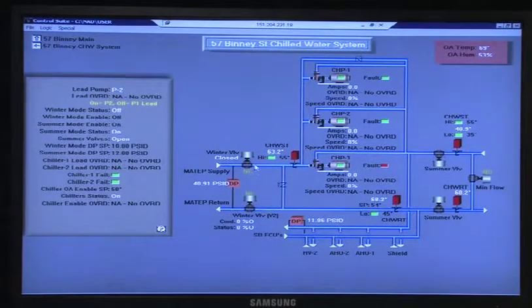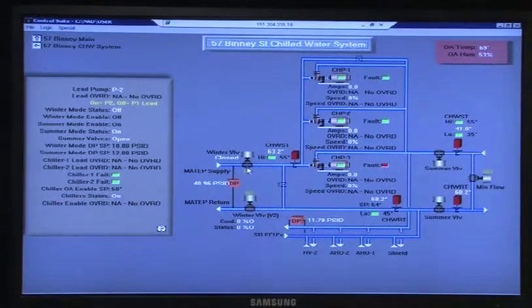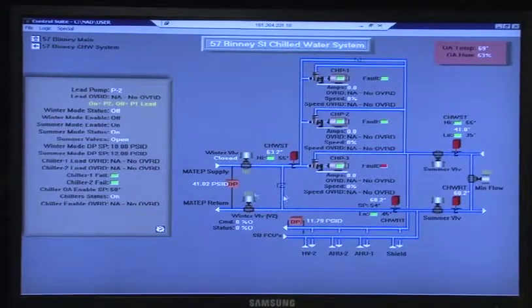So I'm going to talk a little bit about the summer, winter valve business in a minute, how this thing actually is automated and switched over. This is how it all happens. When you switch over from our chillers to MATEP chillers, it's this screen right here. This valve here is normally, not normally anyways, it's not closed, but in the winter mode, this valve will actually be open. So right now we're running in the summer mode.